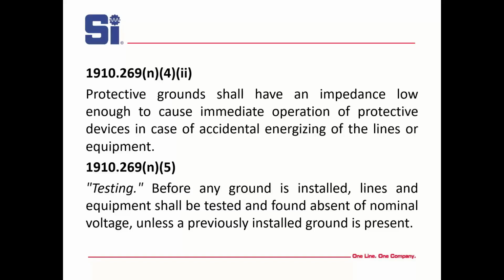And before any ground is installed, lines and equipment shall be tested and found absent of nominal voltage. Now, you could have an induced voltage. That is not what they're talking about. But be aware, if you're working in a substation, that ground has to go on quickly if there's an induced voltage so that it doesn't start arcing.